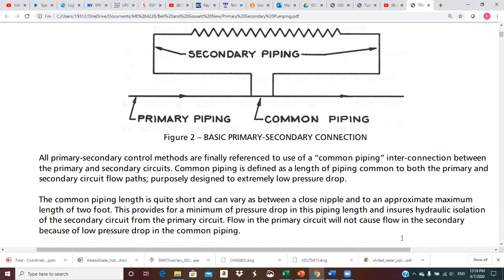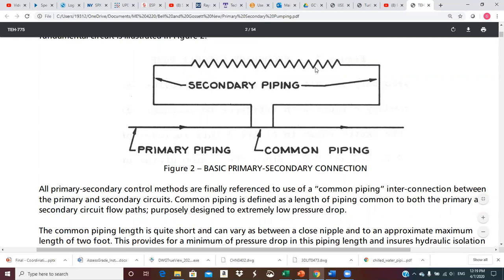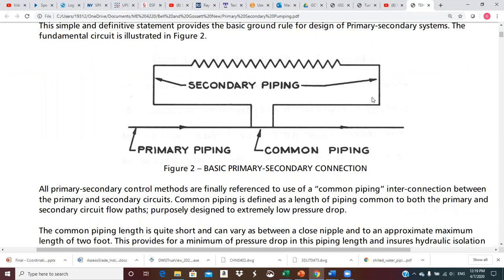Common piping is defined as a length of pipe common to both primary and secondary circuit flow paths, purposely designed to low pressure drop. In the primary, we're pulling out of the primary pipe — we take part of the flow, we go up into the secondary. Let's assume this is a heating circuit; we would go through some sort of a coil, like a baseboard heater under a window. We dump some energy out of this and come back.